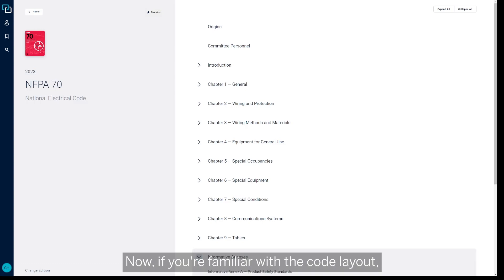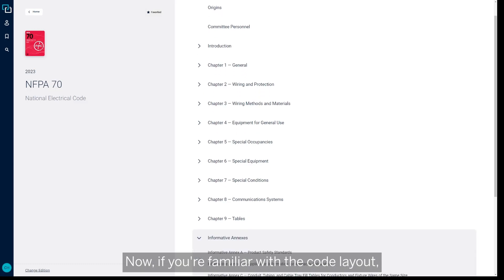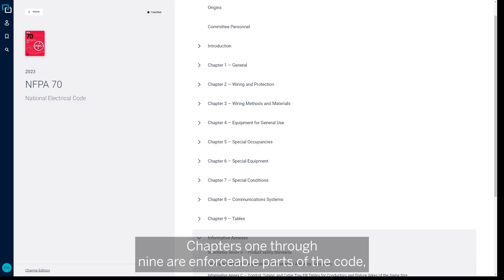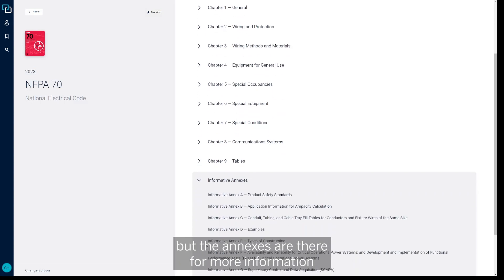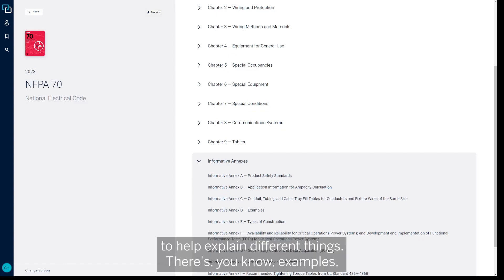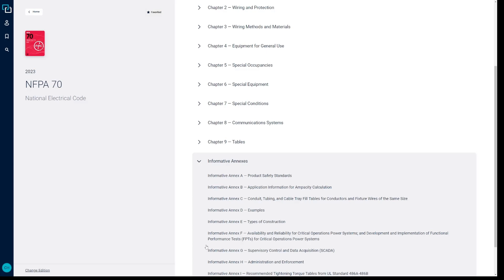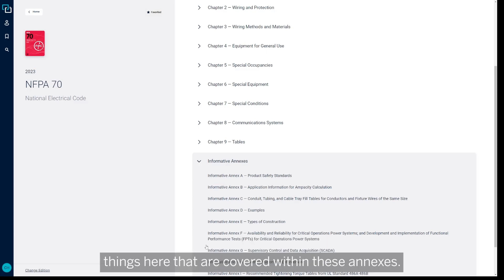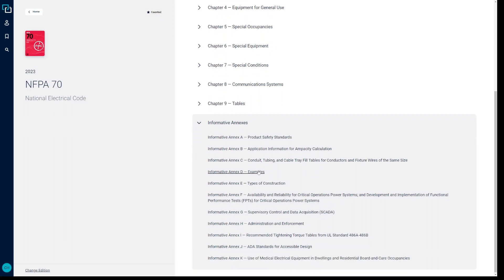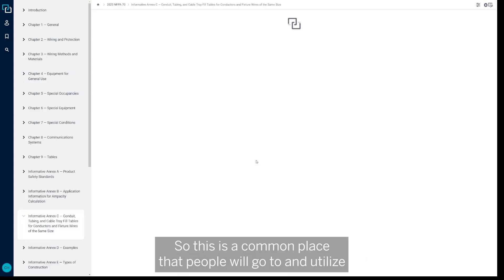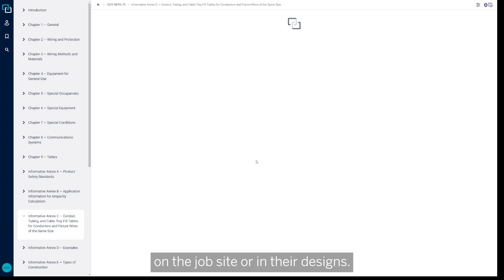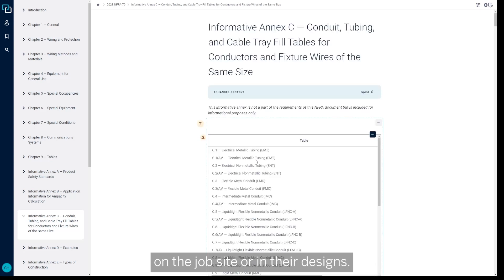Now if you're familiar with the code layout, chapters 1 through 9 are enforceable parts of the code, but the annexes are there for more information to help explain different things. There's examples, administration enforcement—there's several things covered within these annexes, but Annex C is specific to conduit fill. So this is a common place that people will go to and utilize when they initially start thinking about conduit fill on the job site or in their designs.